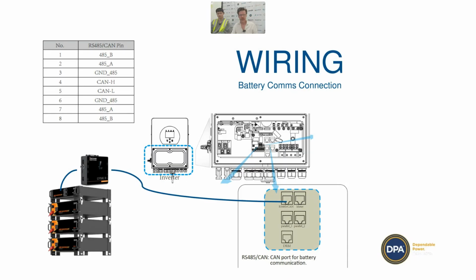But if you look in the top left-hand corner here, this is the pinout for one of the Deye models, battery comms. And you can see that the CAN bus is on 4 and 5, which is the standard. And that's what Discover used for their CAN bus, and that's what Pylontech used for their CAN bus. But you can see that the other pins are taken up with RS485. Specifically on pin 6, we've got ground as RS485. So if you connect the ground from the CAN bus to these ports, sometimes that will mean it doesn't work.